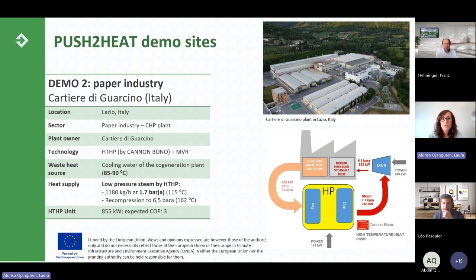Okay, the second demonstrator of Push to Heat is addressing the paper industry as well. In this case, it is located in Italy, in Cartiere di Guarcino. And this is a high temperature heat pump by Cannon Bono, which is combined with a mechanical vapor recompression system to get higher pressure in the steam. In this case, the waste heat is taken from the cooling water of the cogeneration plant of the paper mill, around 85-90 degrees, and the high temperature heat pump will produce steam at 1.7 bar, around 115 degrees, and then this pressure will be upgraded by the mechanical vapor compression system until 6.5 bar, around 162 degrees. The expected capacity is around 850 kilowatt, and the COP of the combined system around 3.